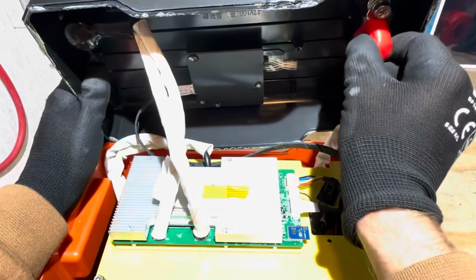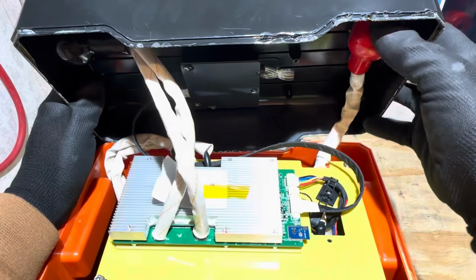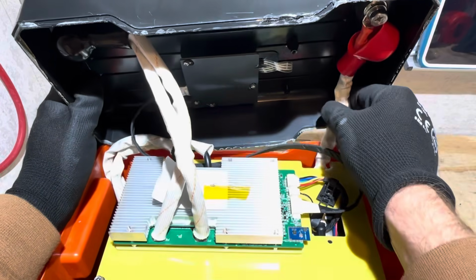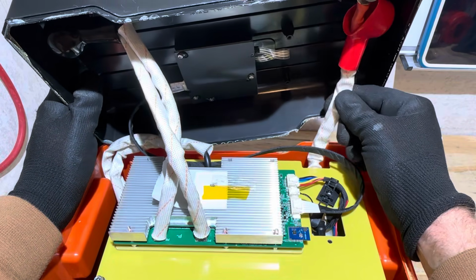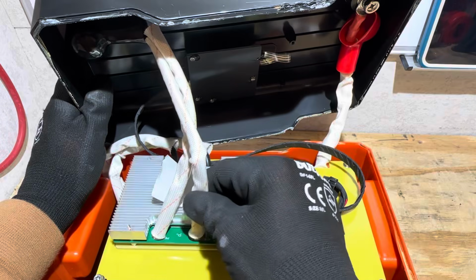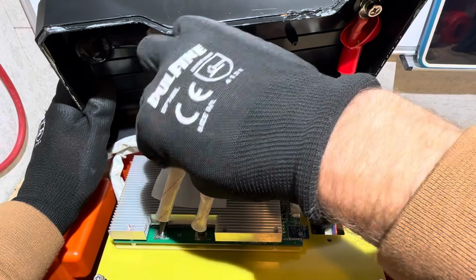They've got some protective caps, and the cap was correctly on there. I pulled that off just to check the tightness. It's got a sheath on it, a fiberglass sheath to protect the outer jacket of the wire. It's tight - that is a soldered connection to the BMS.